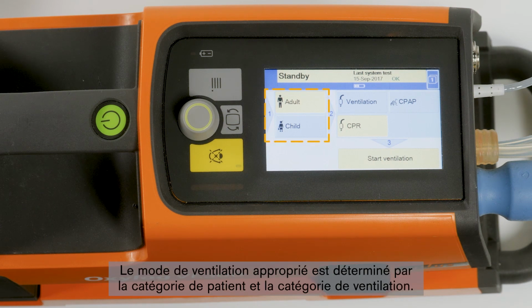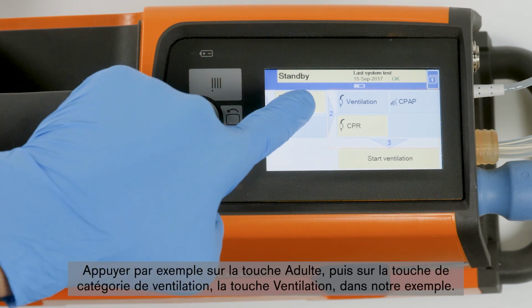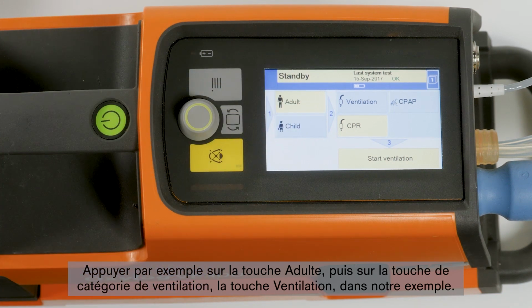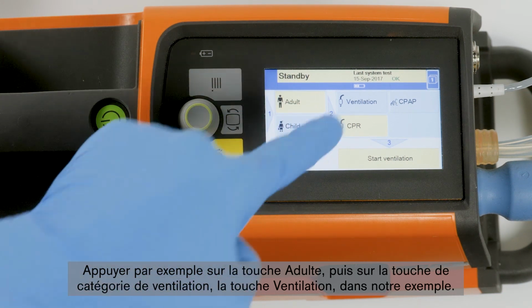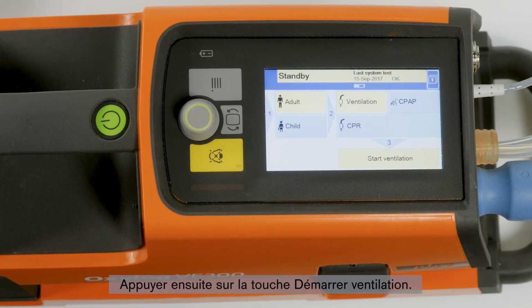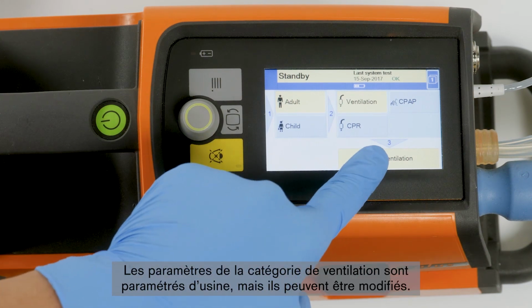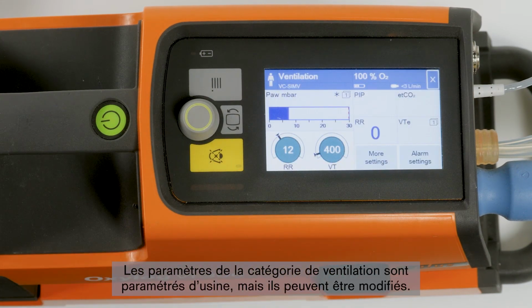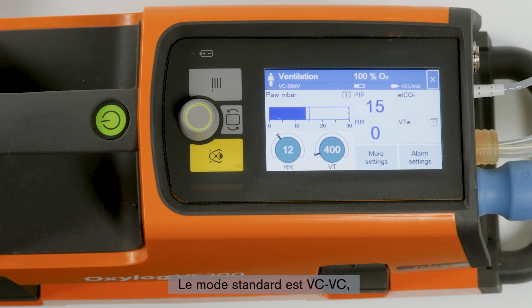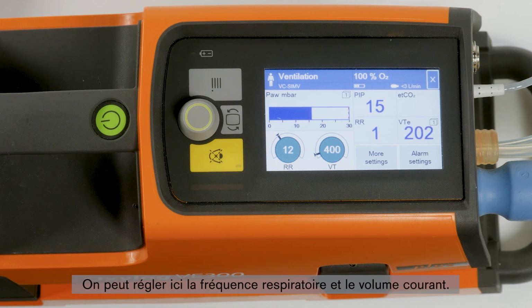The desired ventilation mode is activated by the patient category and the ventilation category. For example, touch Adult and subsequently touch the ventilation category, in this example, ventilation. Then touch the Start Ventilation button. The settings in the ventilation category are preset but can be adapted. Standard is VC-CMV, optional is VC-SIMV. Here, the respiratory rate and the tidal volume can be adjusted.